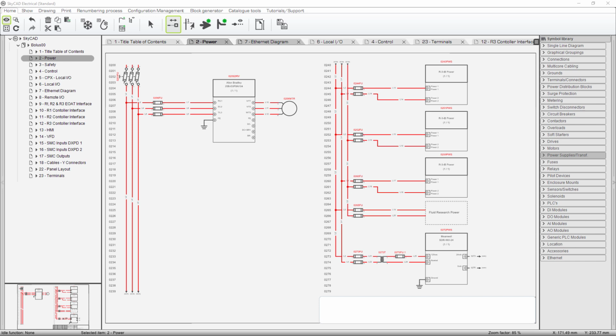Okay, enough said. One three-phase load, the VFD, and now we've got three controllers for the robots, R1, 2, and 3, and we're supplying them basically with 208 or 240, in this case 240. And that's two phases of this power. So notice that we're not running a third phase to these three squares that represent the power connection for the robot. Now that's not the whole robot connection, that's just the power. The interface to the robot from the PLC, that's on another page.